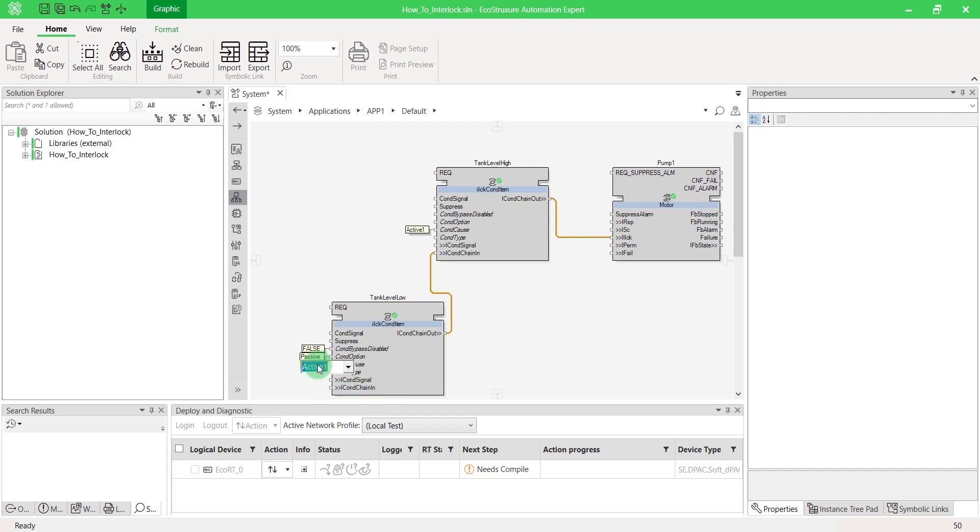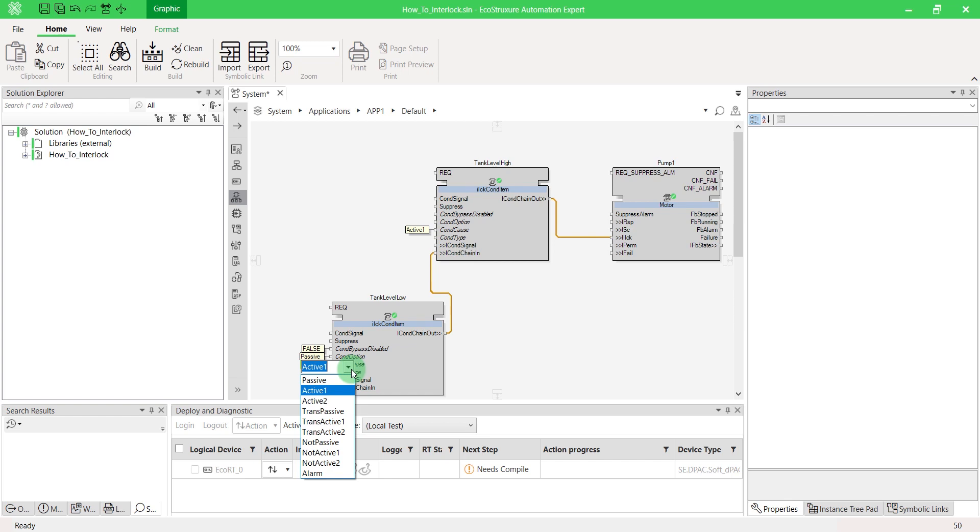CondCause allows you to set a condition on the state of upstream blocks. For example, passive means any motor in sequence is not running. Active one means any motor is running in forward mode. Active two corresponds to reverse mode. Trans passive signifies the input is stopping. Trans active one means it is starting forward. Trans active two means it is starting reverse. Use not passive when any motor in sequence is running. Set not active one or two when it should be a condition other than active one or two. Otherwise, select alarm when any motor in sequence is in alarm condition.